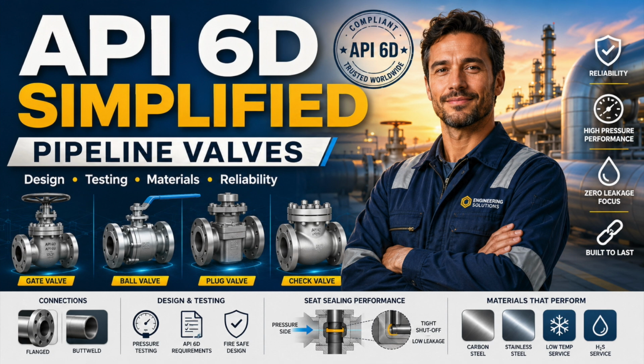Material selection is another area where engineers stop too early. They specify body material and believe the material review is complete. It is not. You need to consider the body, bonnet, cover, bolting, stem, closure element, seat, spring, seal, packing, lubricant, overlay, and coating. A valve body may be suitable while the seat material is not.